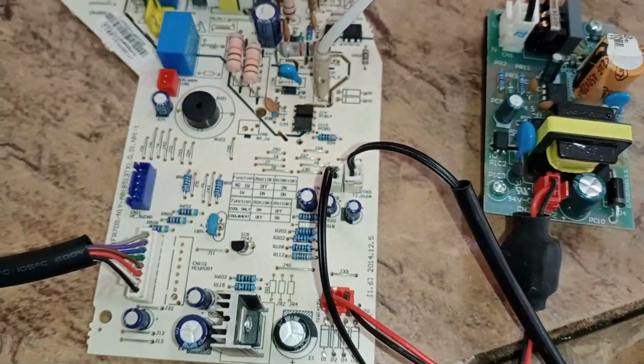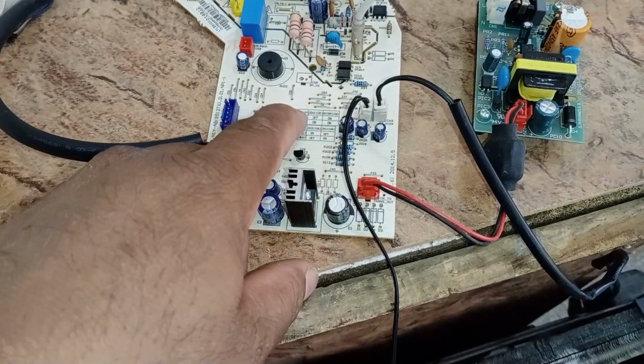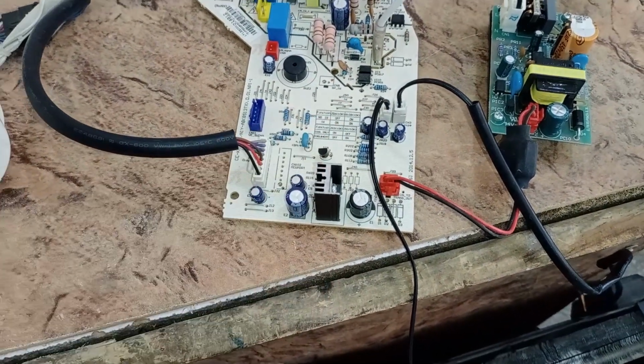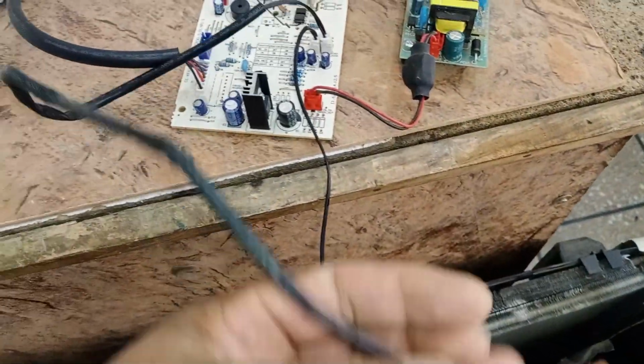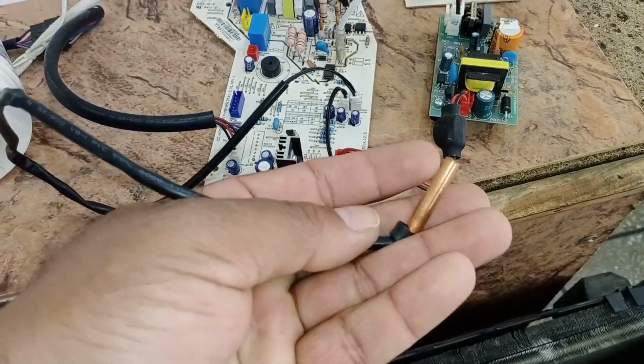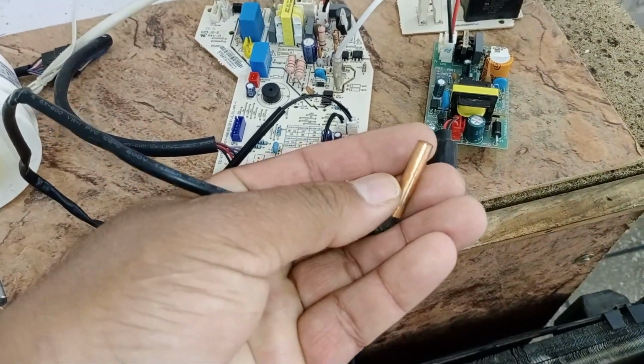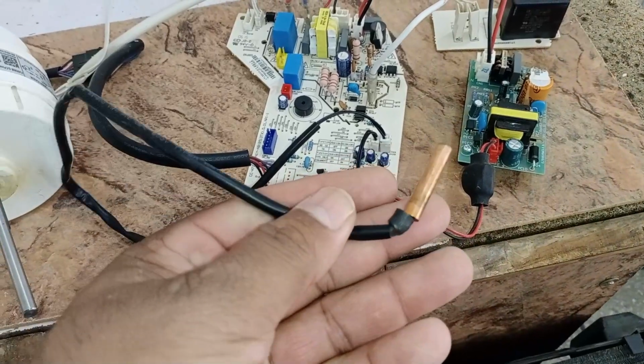Check it carefully. If it's open or short-circuited, it will cause an issue. If there's no 5-volt supply to it, then it's a PCB problem, and you'll need to inspect the PCB. Resolving this issue might fix the problem. The pipe coil sensor works in a specific way and has a designated position where it must be installed. If it's not placed in the exact position, it can also cause issues.